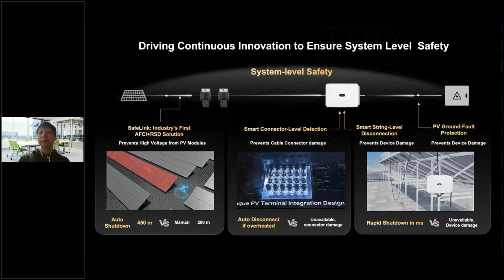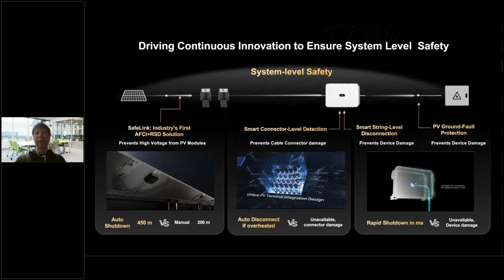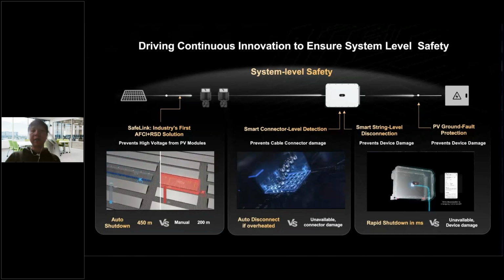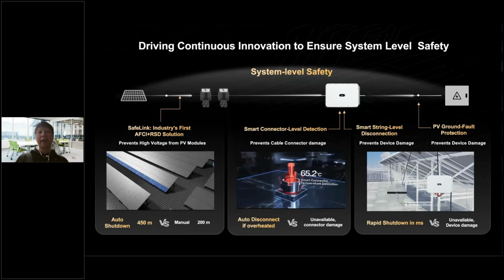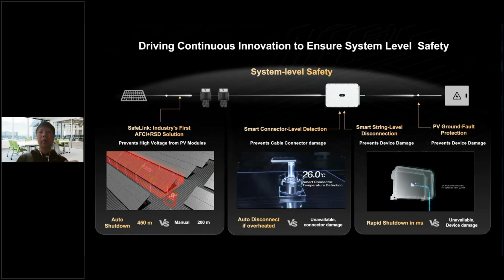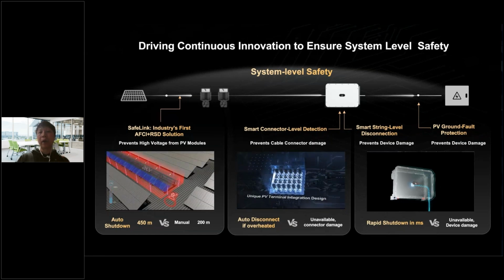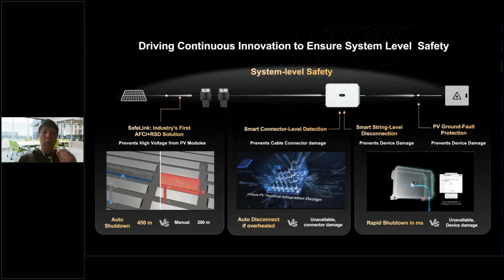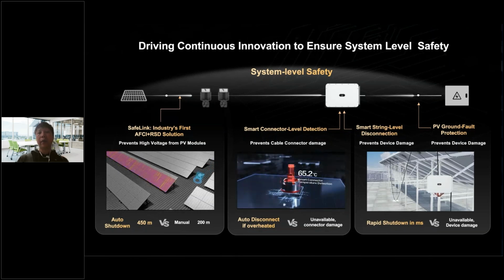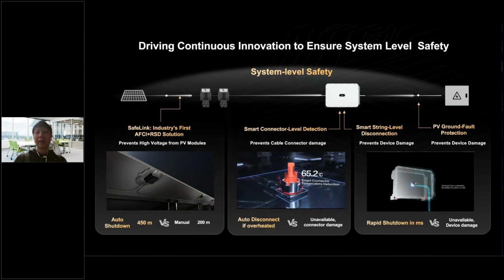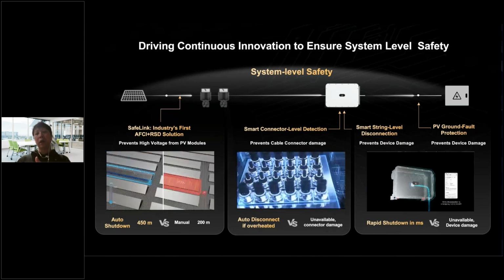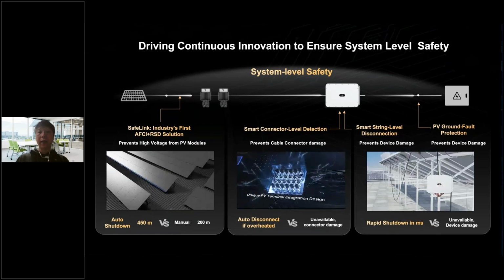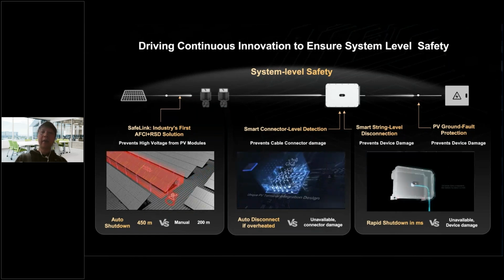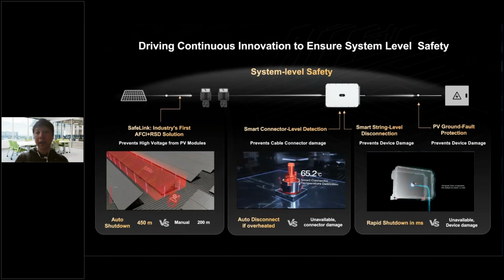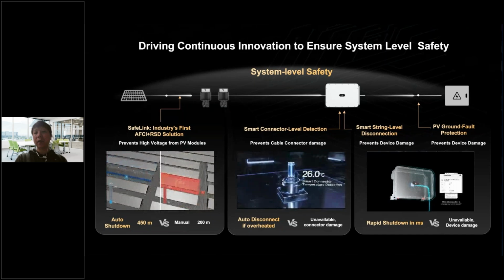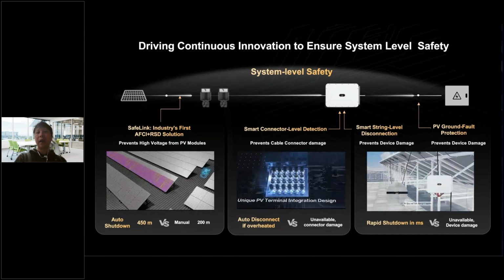on the DC side. The second one is about the connector temperature detection feature. No matter if it's DC connectors or AC connectors, Huawei has a board design, and on this PCB board we have a pad on the back side. This pad is a sensor which monitors the temperature of these connectors in real time, and we have set a threshold. If the connector temperature increases to 95 degrees centigrade, when our sensors detect this temperature, our inverters will shut down to protect themselves. This is a very unique feature, because for C&I inverters, currently we don't see many inverters with this kind of connector temperature detection feature.